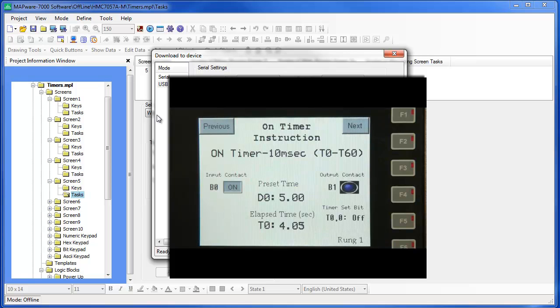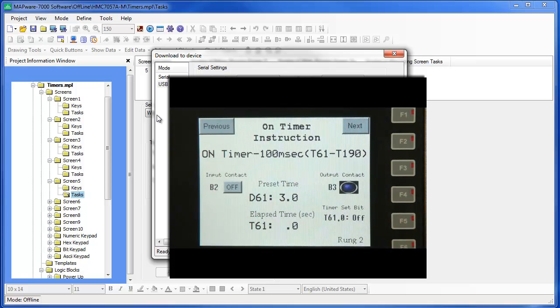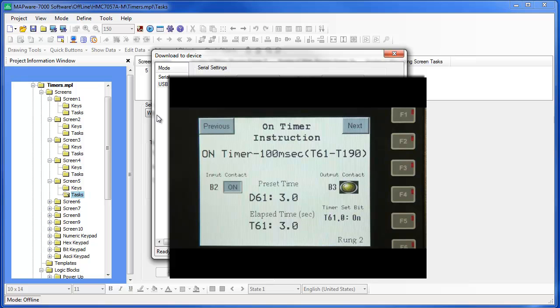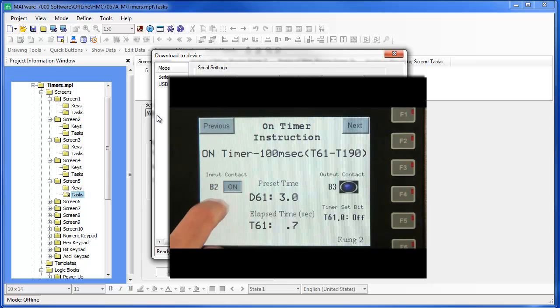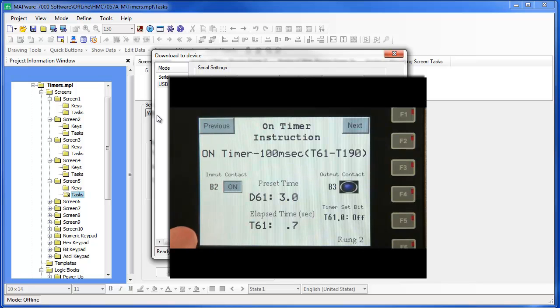Now let's look at the on timer on screen 2. Screen 2 has a preset value in D61 of 3 seconds. Let's turn on B2. The timer increments every tenth of a second until 3 seconds has passed. Notice that output B3 and timer set bit T61.0 turn on once the preset value has been reached. But what happens if input B2 goes off while the timer is still counting? The on timer resets before the preset value is reached, so output B3 does not come on.